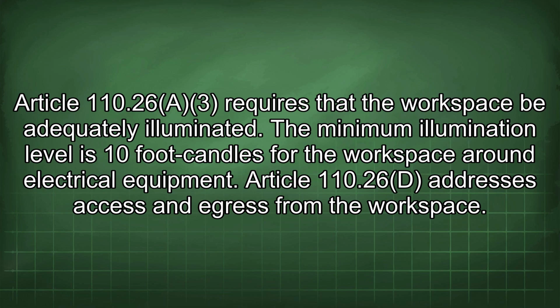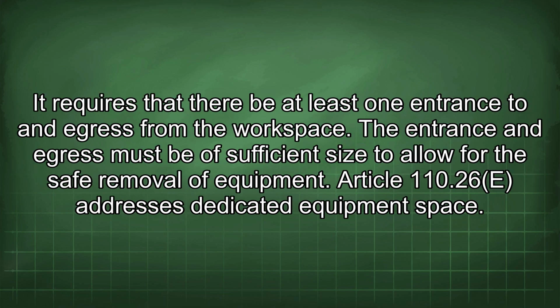Article 110.26 requires that the workspace be adequately illuminated. The minimum illumination level is 10 foot-candles for the workspace around electrical equipment. Article 110.26d addresses access and egress from the workspace. It requires that there be at least one entrance to an egress from the workspace. The entrance and egress must be of sufficient size to allow for the safe removal of equipment.